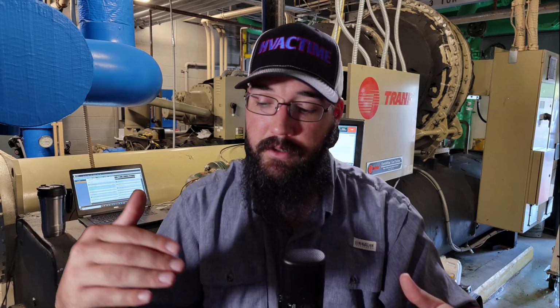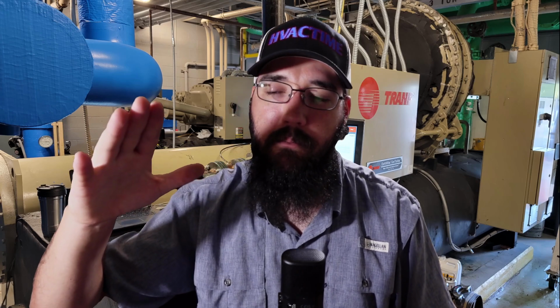So yes, calibration, plunger test. We're listening for the noise. We want to get the top and bottom out sounds, and we want to see how that's moving through there. We also need to be aware that we may pass a calibration, but it may only last for a certain period of time. This is really common: you'll get the alarm, you'll clear the alarm, it'll go through a calibration on the valve to turn it back on, and then it will run like that for most of the day. And it won't be till sometime late that day or that evening before it trips back out again.